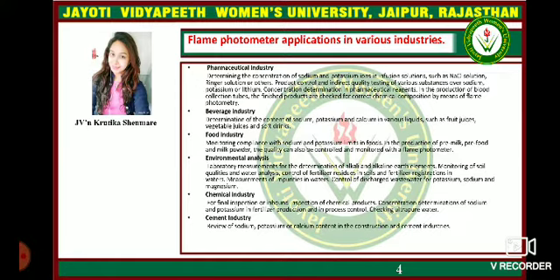Flame photometers can be used in the pharmaceutical industry, beverage, food, environmental analysis, chemical industry, and cement industry. In the pharmaceutical industry, flame photometry can be utilized for determining the concentration of sodium and potassium ions in infusion solutions such as NaCl solution, Ringer solution, or others. It is also used for product control and quality testing of various substances over sodium, potassium, or lithium.